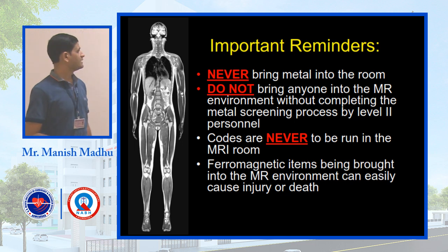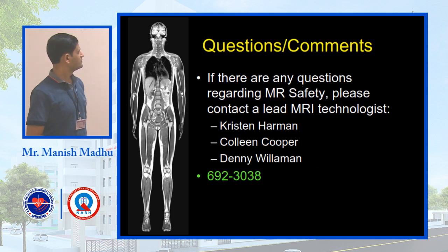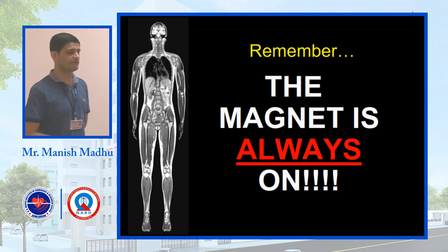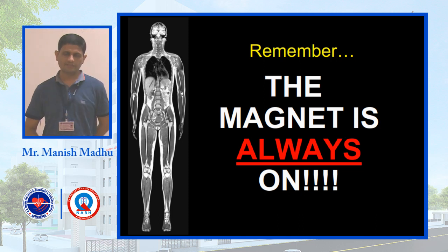Important reminders: never bring metal into the room. Do not bring anyone into the MRI environment without completing the metal screening process by level 2 personnel. Codes are never to be run in the MRI room. Ferromagnetic items being brought into the MRI environment can easily cause injury or death. If there are any questions regarding MRI safety, please ask us when you come to our department. Remember, the magnet is always on. Thank you.